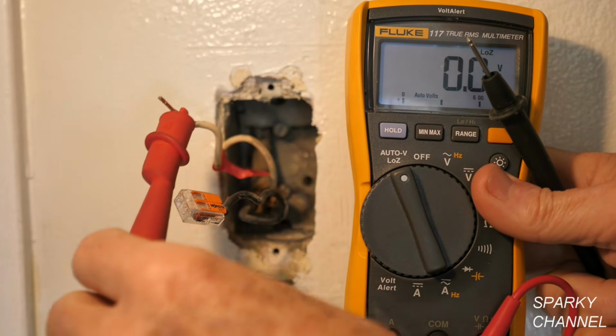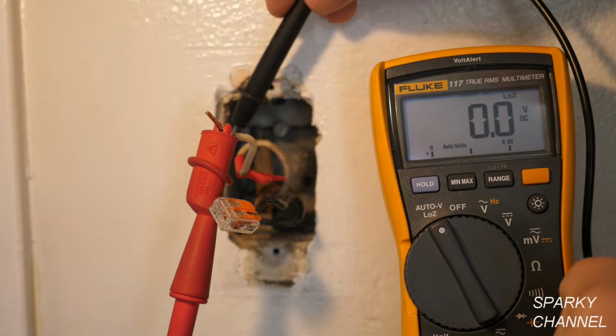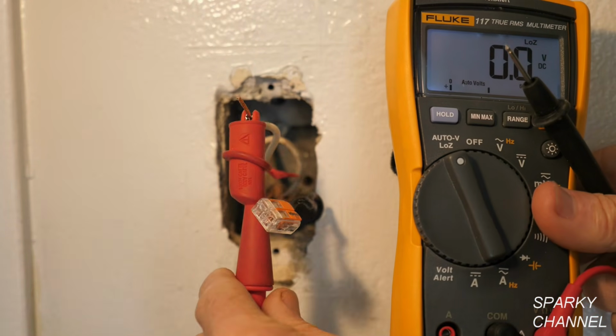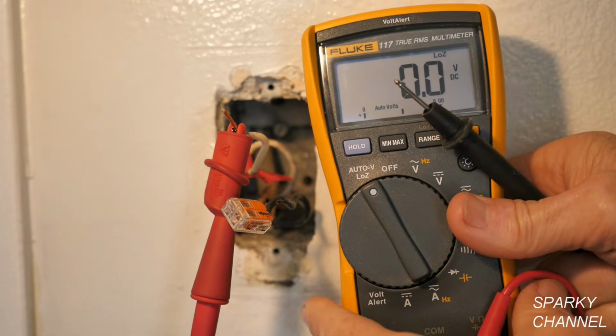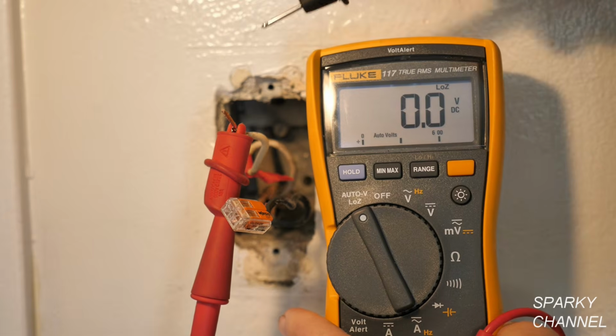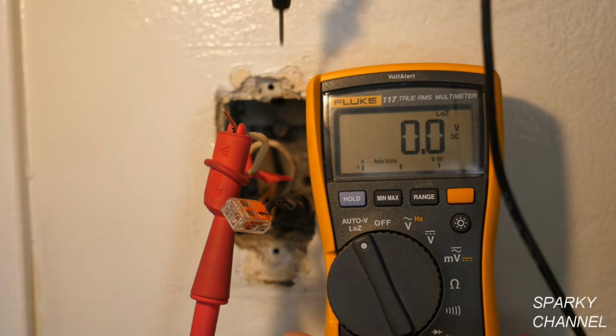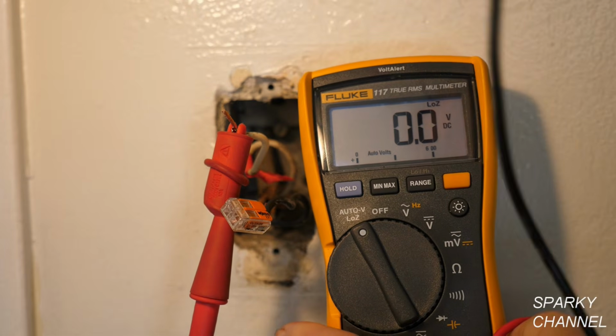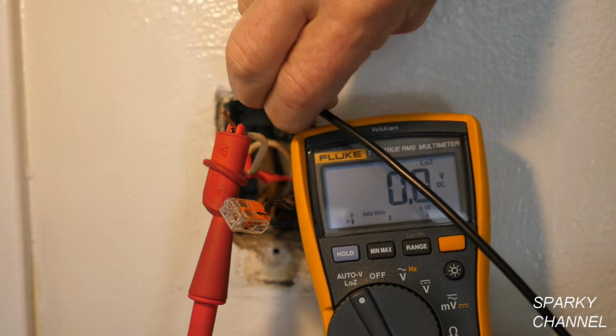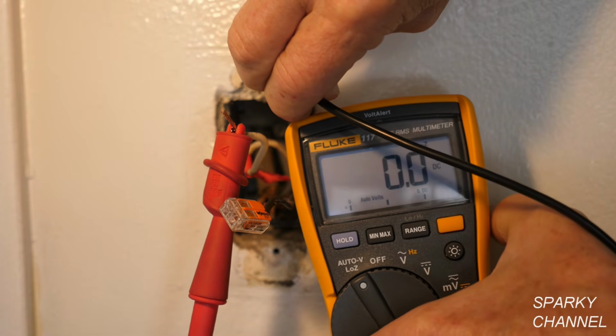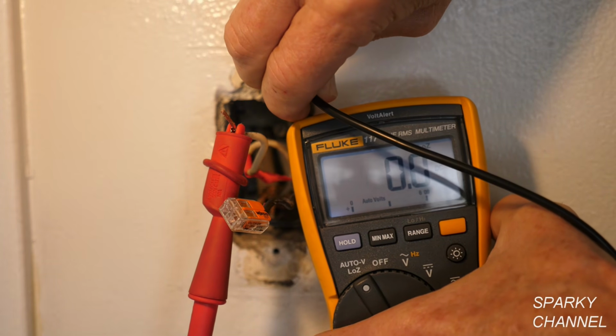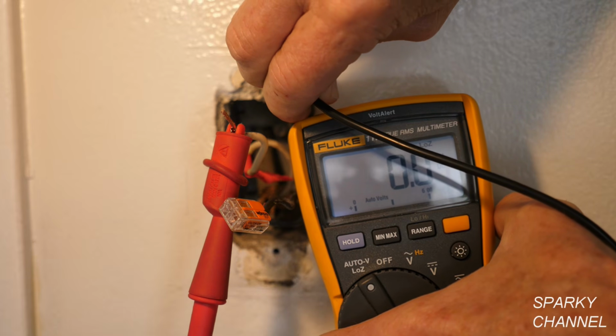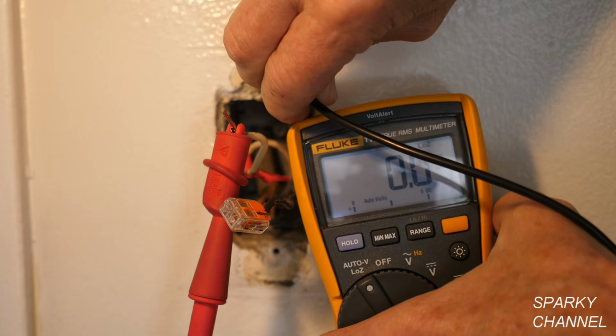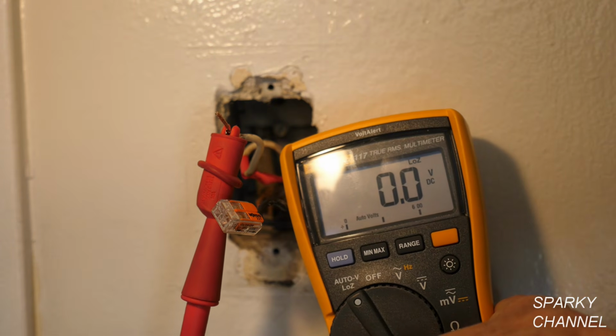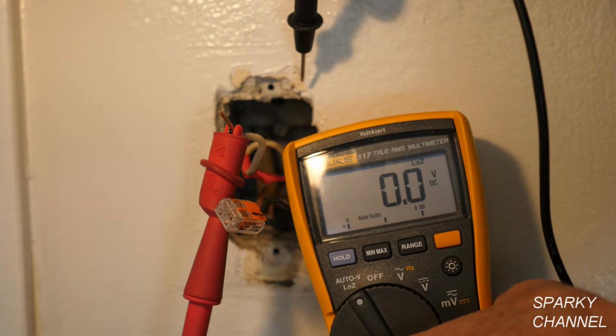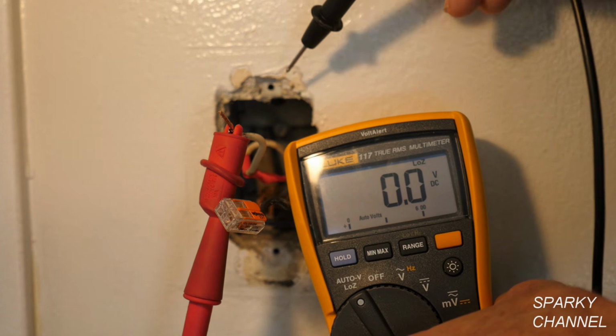For my next test, I've put a piece of red tape back here on the hot wire to designate it as a hot wire. Then I put my alligator clip from my Fluke 117 electrician's meter on the hot wire. I'm going to take this black probe, turn on the backlight, and put it back here on the metal, and I'm getting 0.0. That means the metal box does not provide a path to ground. It doesn't provide a path back to the load center. So I'm not going to be hooking a grounding pigtail up to this box and using that, which I would do if this was showing a ground.